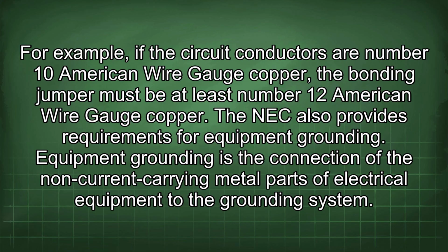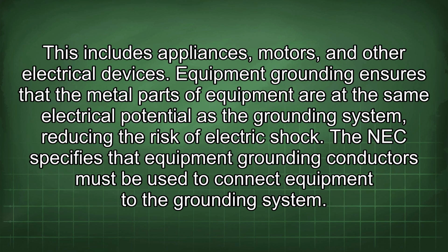The NEC also provides requirements for equipment grounding. Equipment grounding is the connection of the non-current carrying metal parts of electrical equipment to the grounding system. This includes appliances, motors, and other electrical devices. Equipment grounding ensures that the metal parts of equipment are at the same electrical potential as the grounding system, reducing the risk of electric shock. The NEC specifies that equipment grounding conductors must be used to connect equipment to the grounding system.